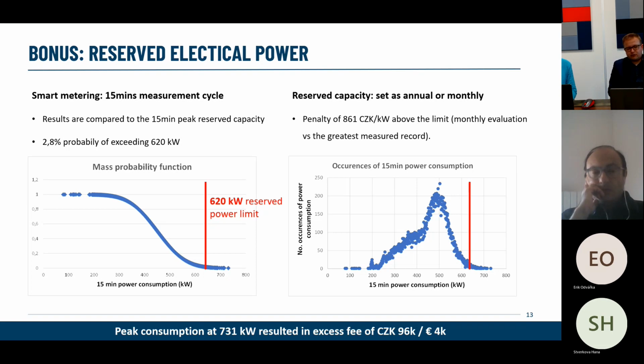So the company that I would like to discuss at this slide, as a big consumer, is connected to the high voltage connection point at 22 kilovolts, right? It's not a domestic connection point at 400/230 volts, but 22 kV. So they are obliged to actually measure the power consumption within 15-minute cycles. So you've got this continuous electrical meter, and it starts measuring at 0000. It stops the first cycle at 0015. And then every 15 minutes, it integrates the energy spent within that 15-minute cycle, and then calculates by division by these 15 minutes what was the actual power drawn in that interval. Average.